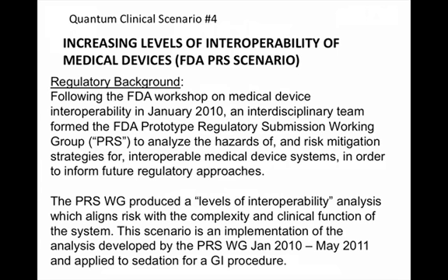We called it a prototype regulatory submission because our goal was to create an educational or research regulatory submission with research devices and potentially devices on the market. This is in stark contrast to a typical regulatory submission in which devices that are ready to be marketed are presented to the FDA for clearance to market those devices for use.